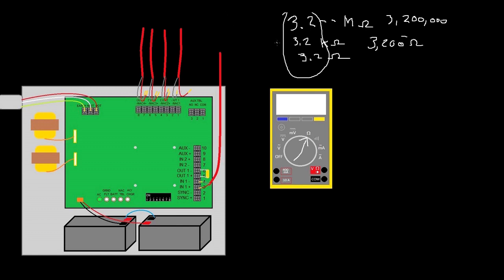Okay, well even if you know that this is 3.2 megaohms or 3.2 kilohms, how do you know if that's a ground fault? How do you know if that's a problem? Well, it's a good question and in some cases you may not know. There are some manuals that I have seen that will give a reading for what their ground fault threshold is on the panel.